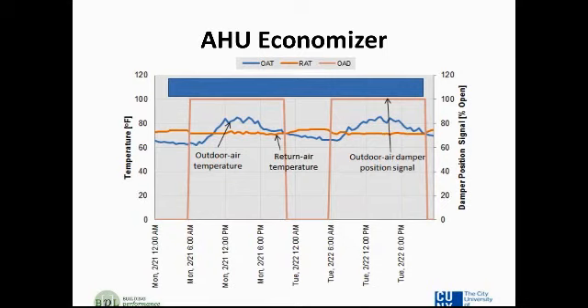You could have the outdoor air damper fully open during that period, but then when the outdoor air temperature exceeds the return air temperature, you would want to close down your damper to minimum position and only bring in as much outdoor air as is needed for ventilation. So that would be a much better sequence of operations.